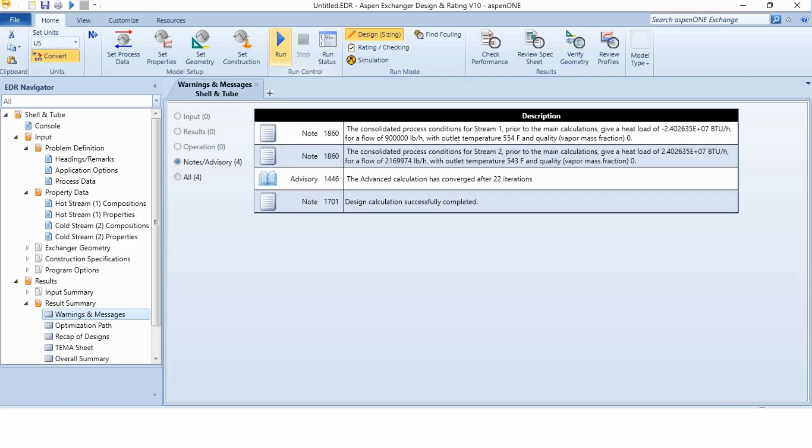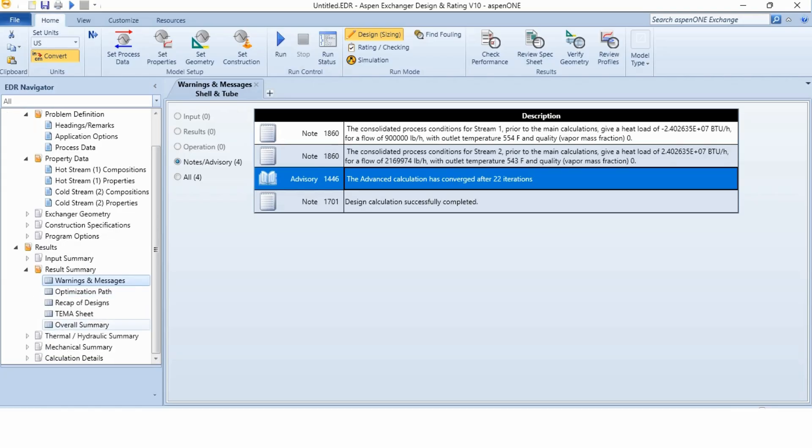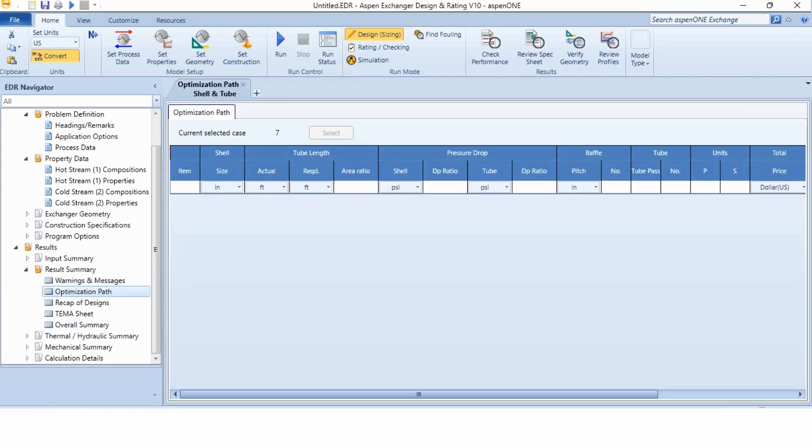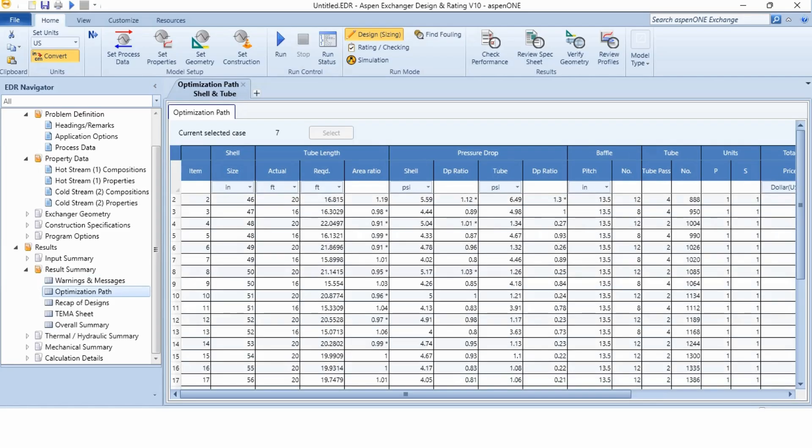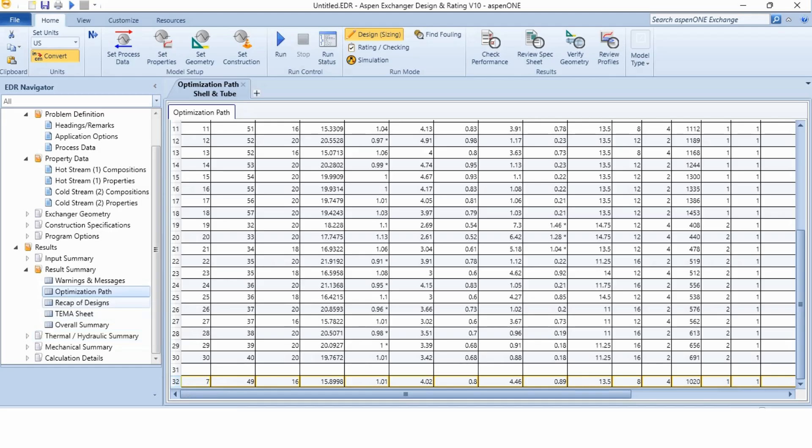Now, you can see there are no input warnings, there are no results issues, there are no operation warnings and all of the things is now okay, there are no issues in the system. So, it means that we can use the design which has been reported to us. After 22 iterations, the design has been converged. Obviously, I have skipped a few parts and now we can go to the optimization path to check the designs. These are the evaluated designs by the Aspen. There are 30 designs that are evaluated and out of which the seventh design is declared as the best design of the system.